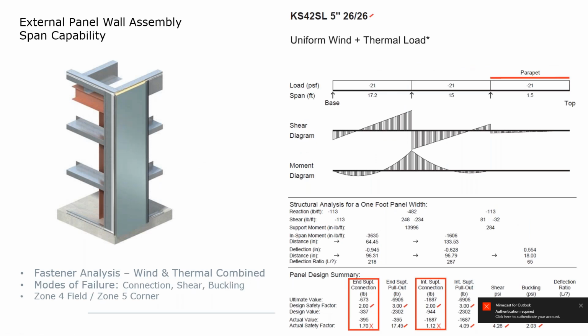Again, just an example here of the components and cladding that we provide on the design to understand your fastening and where you're going to attach these panels. And again, to reiterate, on the cold storage side, we do this a lot more than we do on the industrial side because of the thermal temperatures involved and that deflection that occurs in the panel as the temperature is brought down on the interior of the building. So this determines the steel and the girt locations, and that's something you'd want to do on the front end of your design once you know the interior temperature of the building.